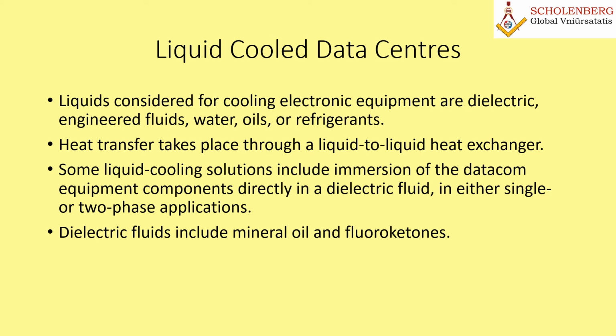So what are the fluids or liquids used to cool the datacom equipment? Well, with increasingly dense datacom equipment packaging, some components may require liquid cooling to maintain the environmental specification dictated by the manufacturer. Liquids considered for cooling electronic equipment are dielectric engineered fluids; it could be refrigerant, it could be oil. The heat transfer from liquid cooled datacom equipment or components to the datacom facility generally takes place through liquid to liquid heat exchangers.